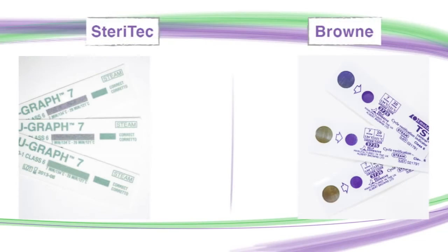Let's take a look at some products that have demonstrated a pass result, which would have been recorded as a satisfactory test for sterility assurance and kept as a permanent record. As you can see, this Steris Brown test has been exposed in an autoclave and shows a pass result as indicated by a yellow to blue color change. The bottom two tests have been partially exposed. They have clearly been through a failed sterilization cycle as indicated by an incomplete color change.